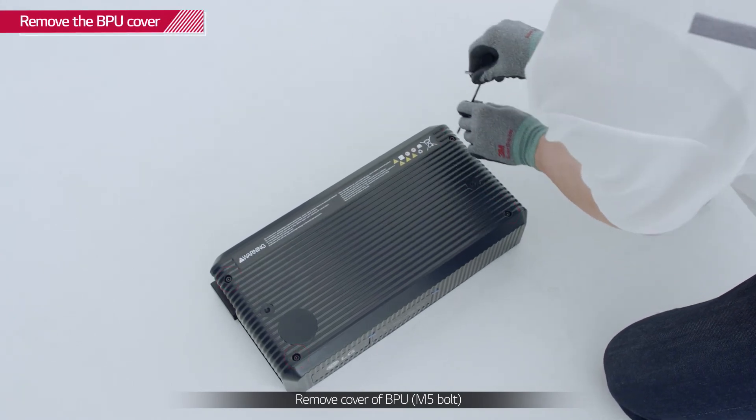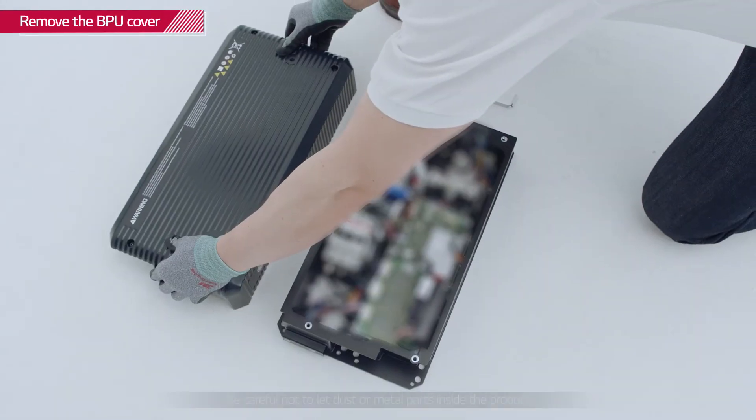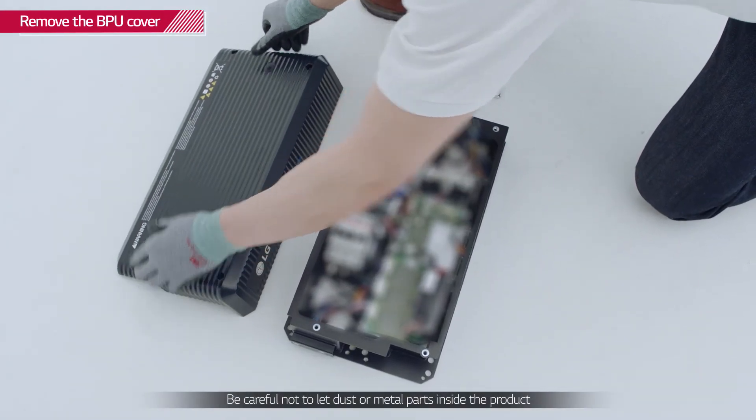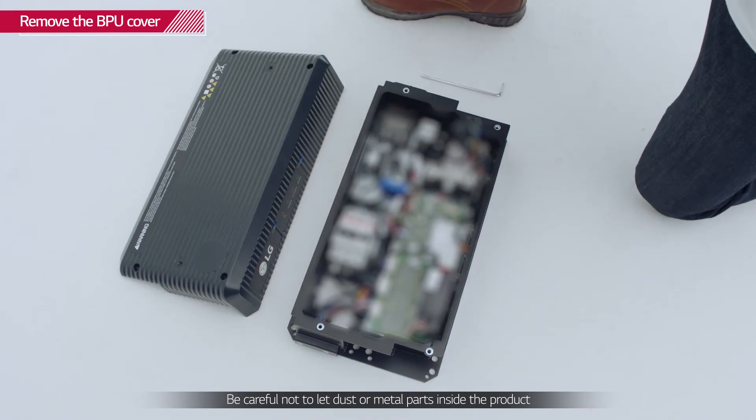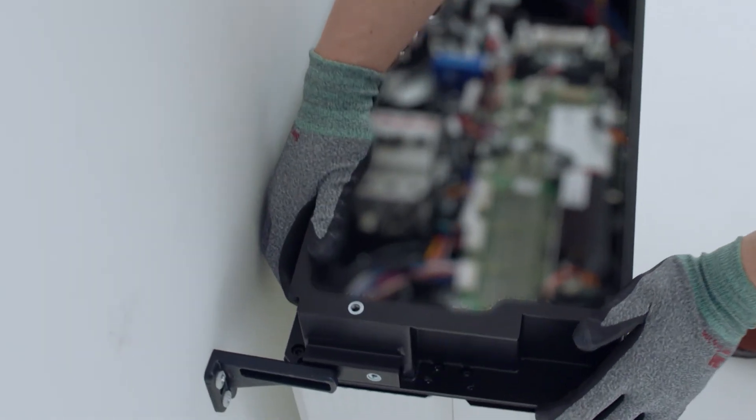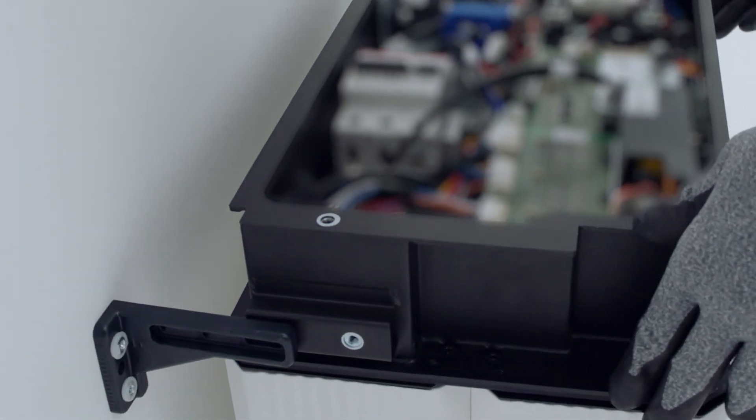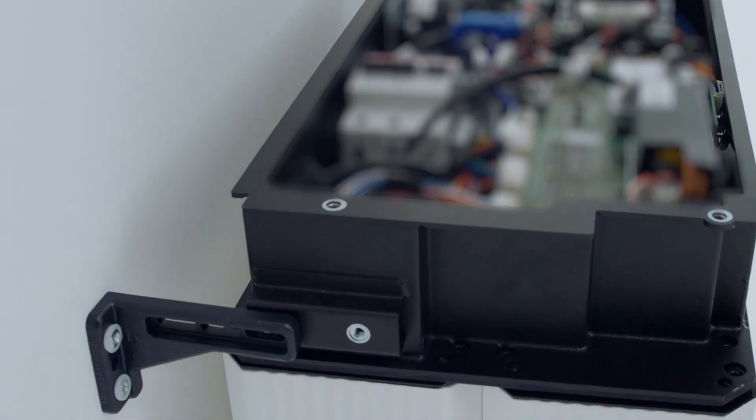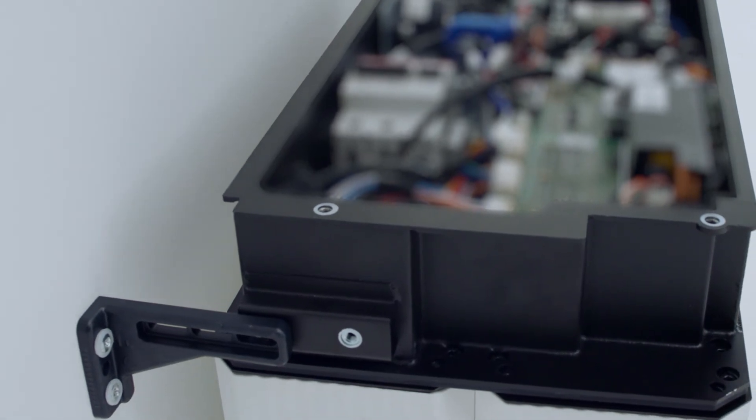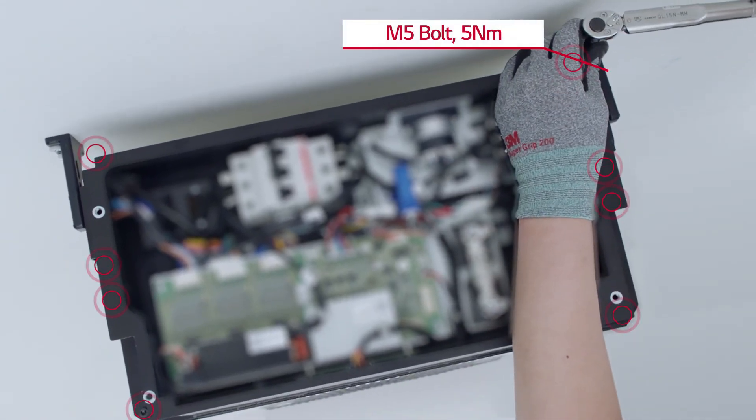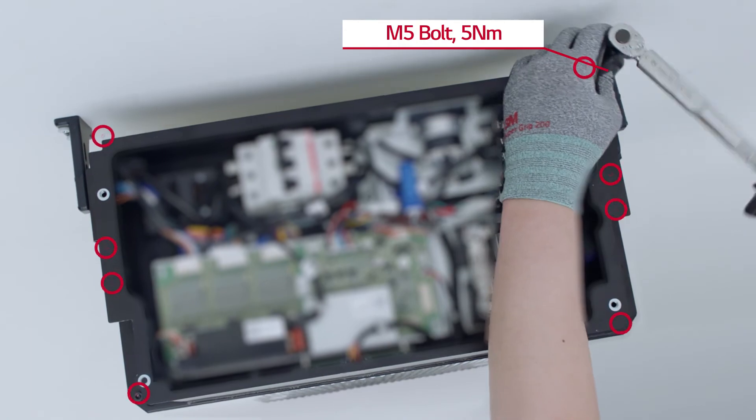Remove the BPU cover by loosening the four screws at each corner of the top cover. With the cover removed, place the BPU on top of the battery modules and fasten it with eight M5 bolts with a torque of 5 Nm.